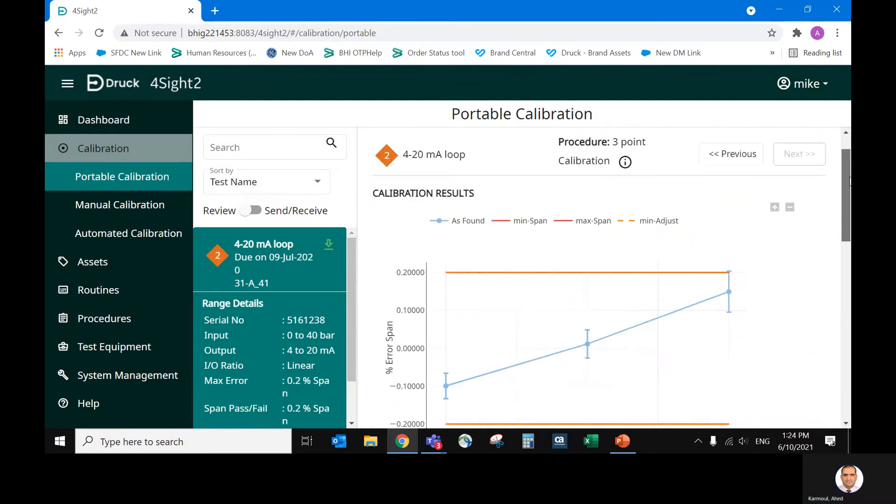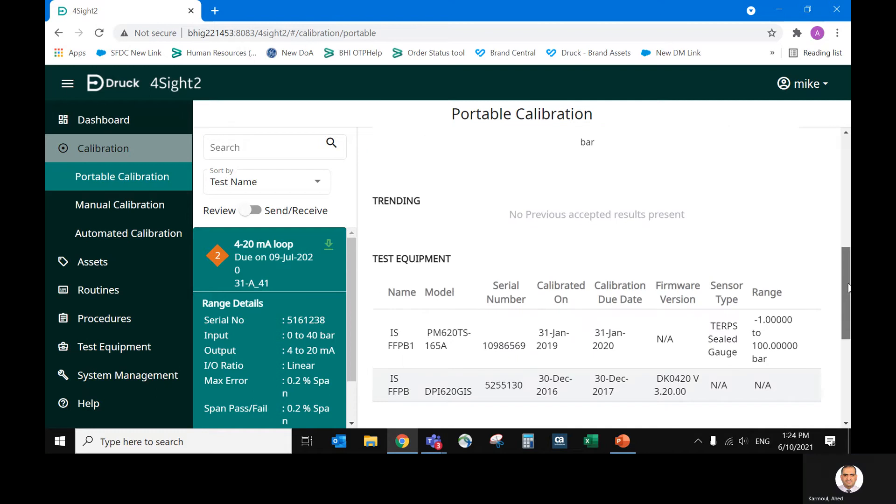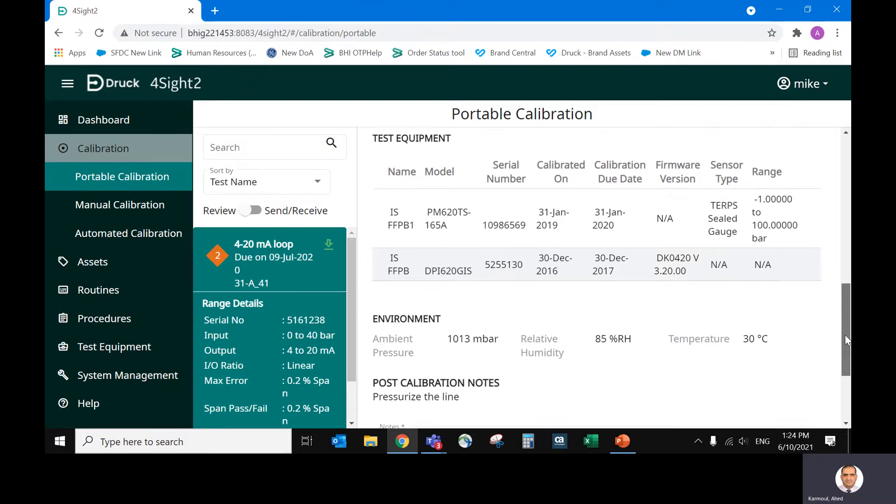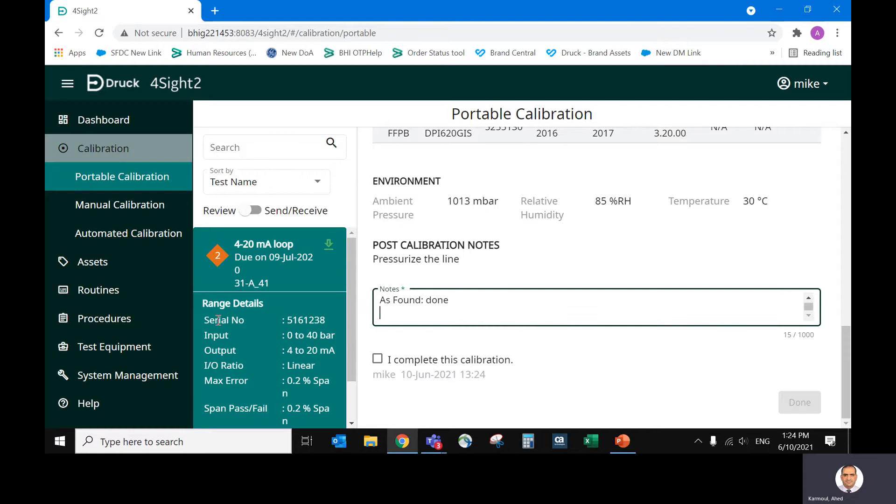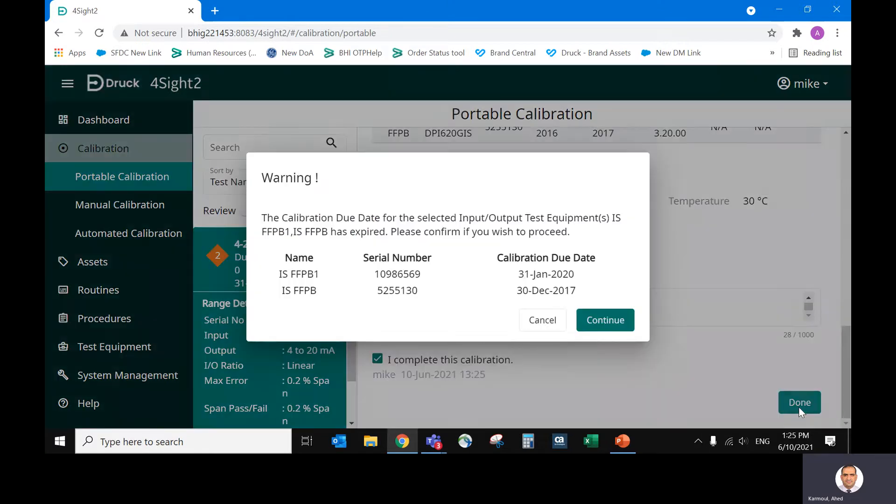And the summary will show you that it's done with these devices. This is the pressure module. This is the Genii, which measures the milliamps. And this is the note we added in the calibrator successfully. I completed this calibration. This will have a digital signature for Mike at this date and this time that he performed the calibration.